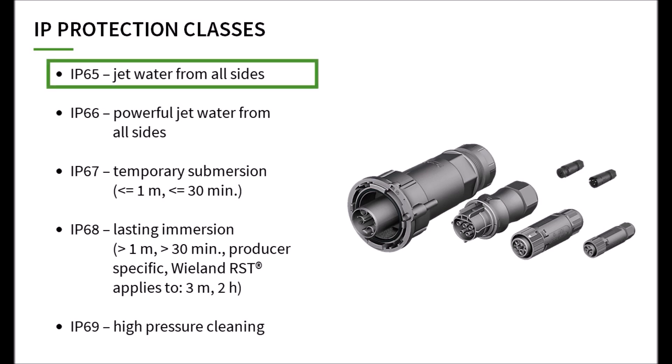5 specifies the protection against water spray from a nozzle at any angle. 6 specifies protection against strong jets of water from all sides. 7 specifies the protection against temporary immersion in a maximum depth of 1 meter for a maximum of 30 minutes. 8 specifies the protection against permanent immersion.